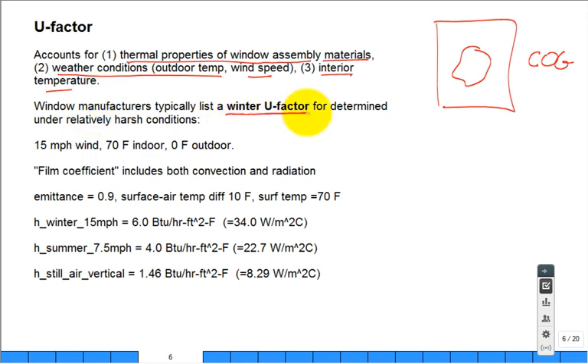We're not going to do the edges, we're just going to go in the center of the glass - sometimes it's C-O-G, center of glass. Just straight through the middle of the glass. It depends on the outdoor temperature, outdoor wind speed. The engineers that report these have standardized so everybody picks the same one and they can report different windows to the same conditions. And the same interior temperature. They typically list the winter U-factor.